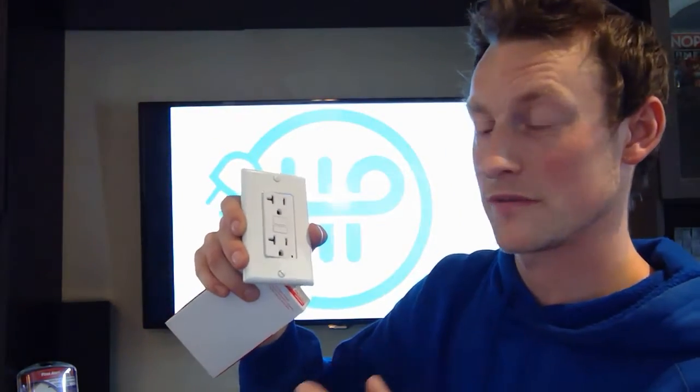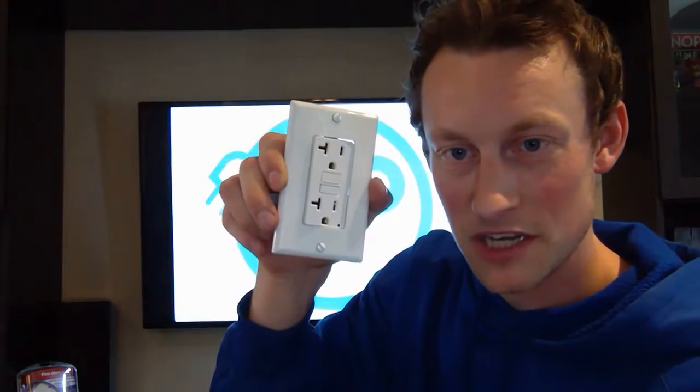Now, if you have a 20 amp device and it's going to draw more than 15 amps, and manufacturers know that, it's going to come with a T slot. And it's only going to fit in these, and it will not fit in a 15 amp. I'll show you 15 amp just a second here. Here's an unboxing of a, please don't sue me, Legrand. You got a great product here at Legrand. This is what we provide.